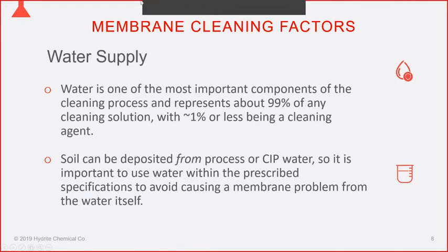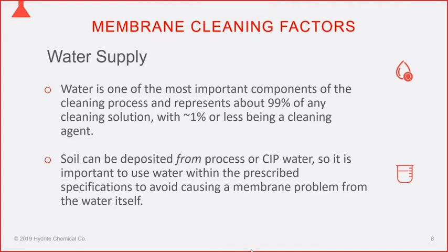Water supply is a very important factor. Water can be about 99% of your cleaning solution. Soil can be deposited from the product being processed or from the water used to clean the membrane. Most major customers cleaning membranes today use polished RO water — low in mineral content, considered soft, and generally treated with a biocide or UV light to control microorganisms.